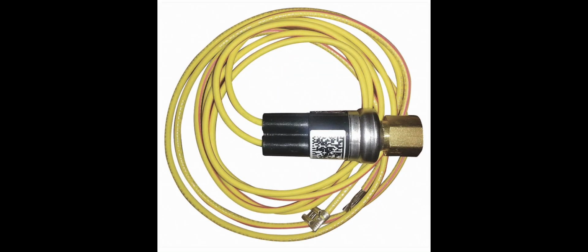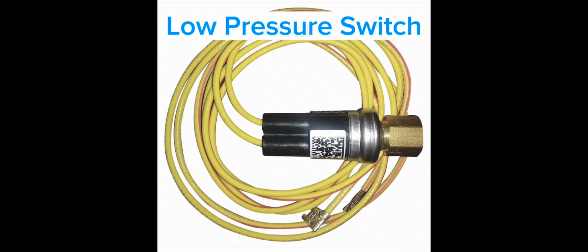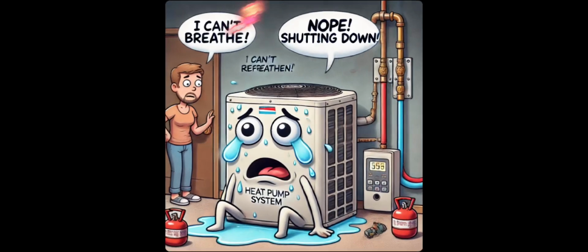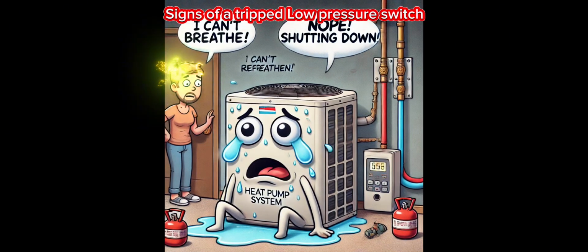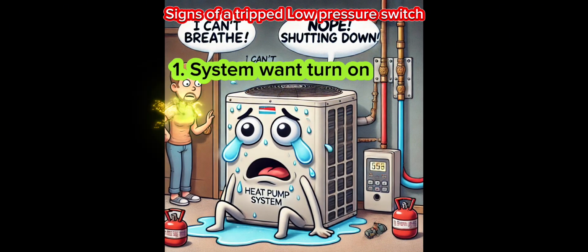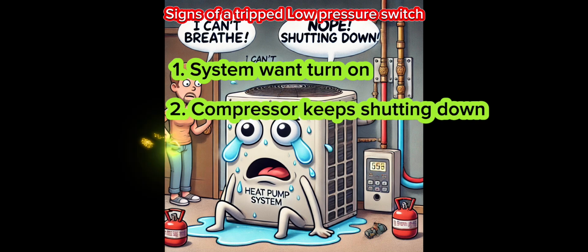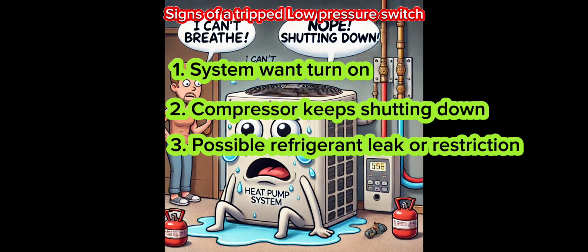The low pressure switch, or the LPS, is a safety device that shuts off the compressor if refrigerant pressure gets too low. It's usually due to a leak or restriction in the system. Running a compressor with low refrigerant can cause severe damage.